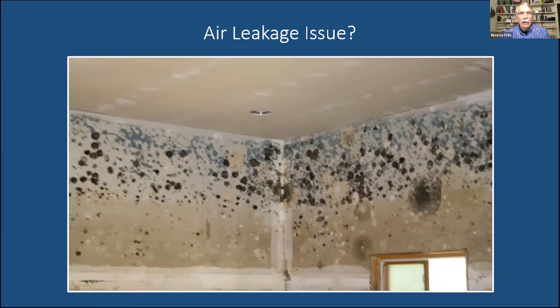Condensation on the windows. We're called out to solve these problems a lot of times, especially in high-end fancy homes, that have a lot of complicated air barrier issues going on in them, and some very fancy ducting systems going on. It's a ventilation issue also much of the time, but whatever it's causing, a lot of times there are air leaks involved, so that we get our humidity lines and our temperature lines that cross, and we get dew point type phenomena like this, condensation. This indeed can be a picture of an air leak in a building.